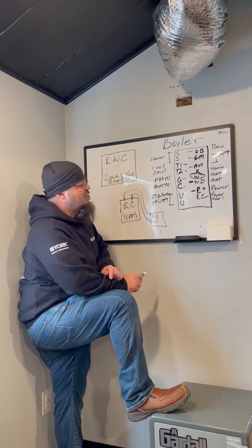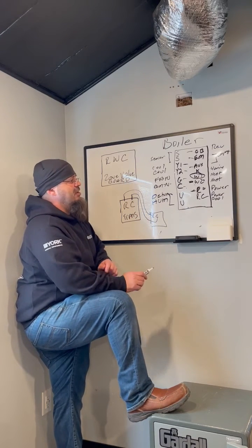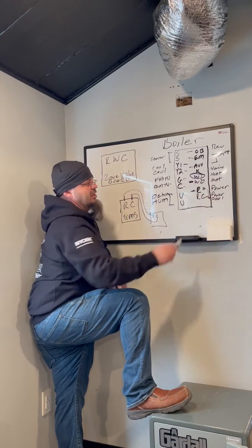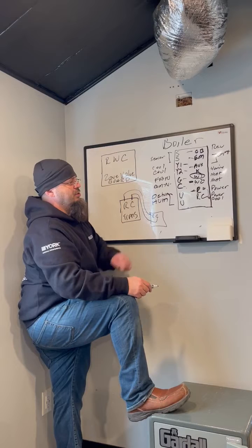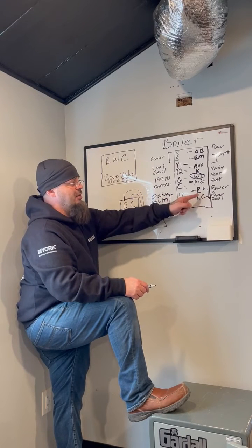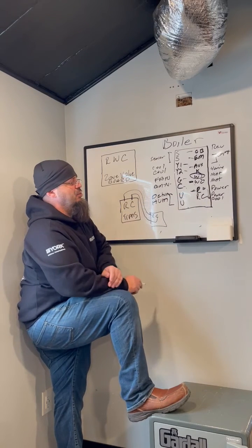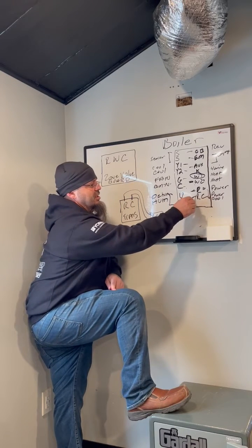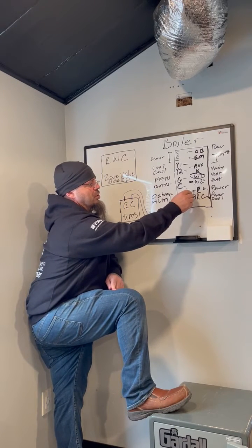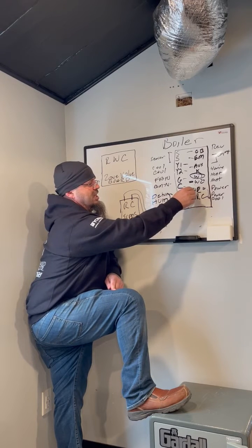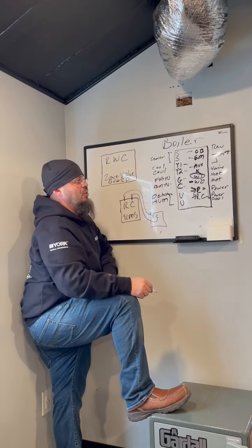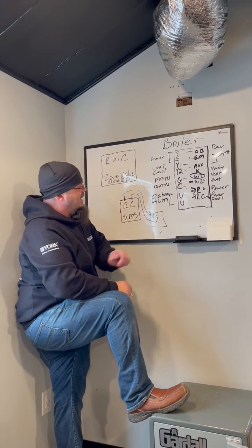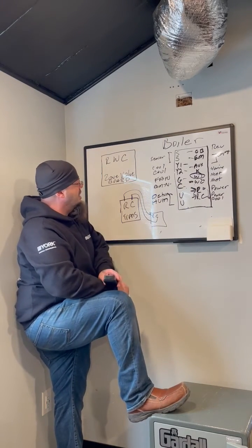And then you would have to wire separately. In a Honeywell, you would put your toggle switch down, and then it would be two separate wires, and then you would run your power to here, and you would run one side of TT to R and the other side to W. So a little advanced to do that. There's a little bit going on there.